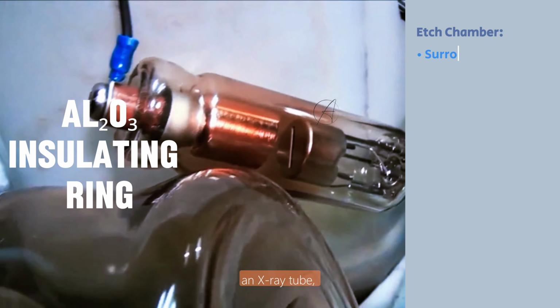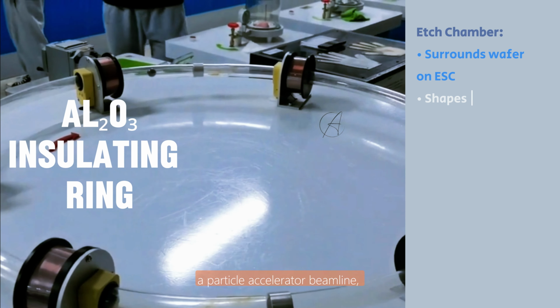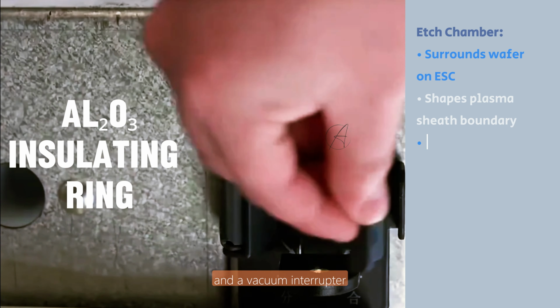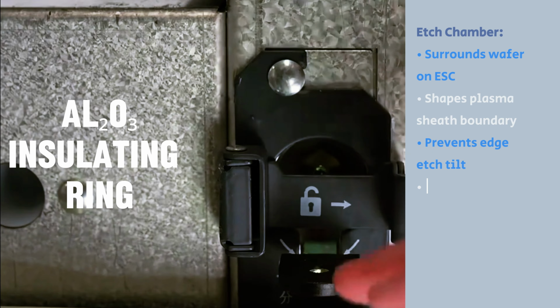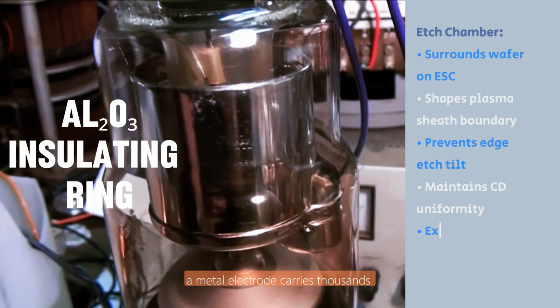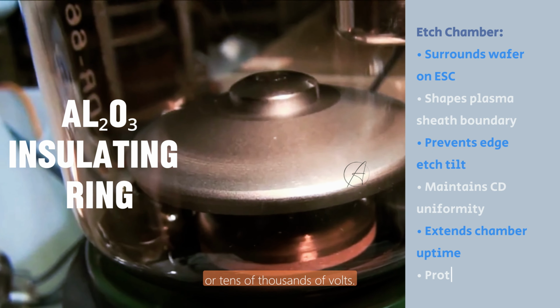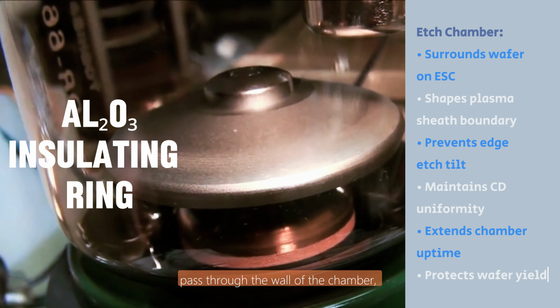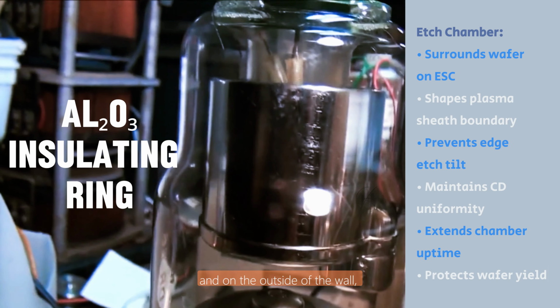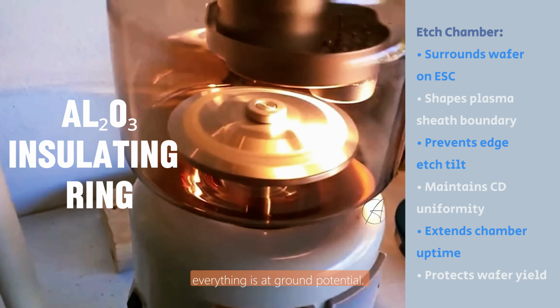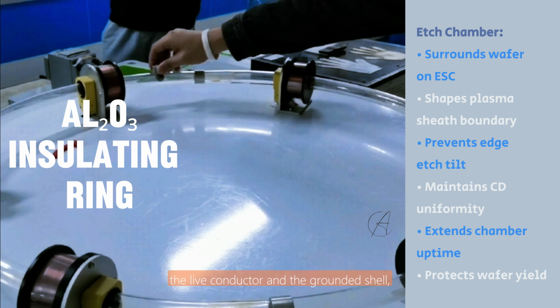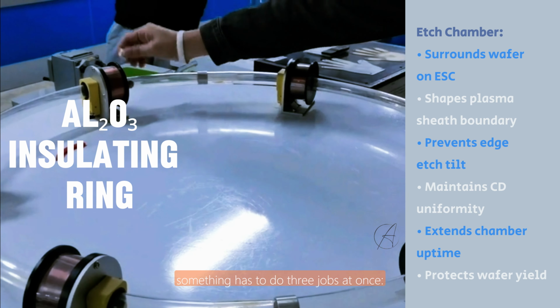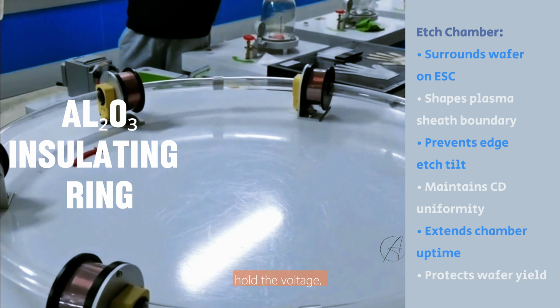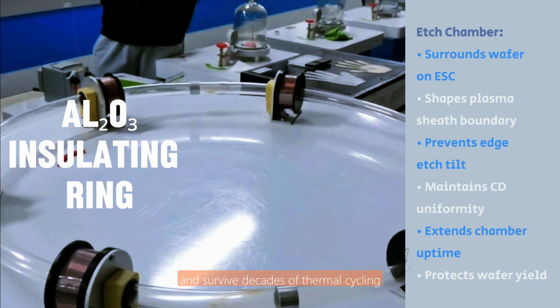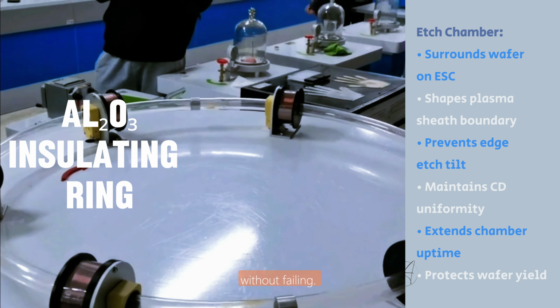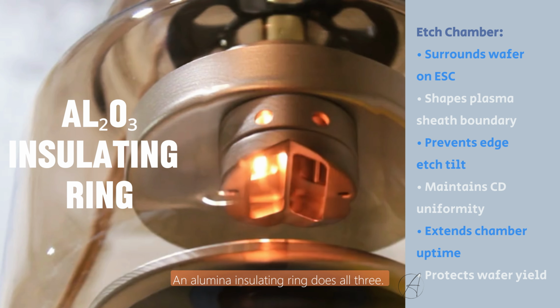Picture a vacuum chamber. An X-ray tube. A particle accelerator beamline. A vacuum interrupter in a high-voltage switchgear. Inside each of them, a metal electrode carries thousands or tens of thousands of volts. That electrode has to pass through the wall of the chamber, and on the outside of the wall, everything is at ground potential. At the interface between the live conductor and the grounded shell, something has to do three jobs at once. Hold the voltage, seal the vacuum, and survive decades of thermal cycling without failing. An alumina insulating ring does all three.